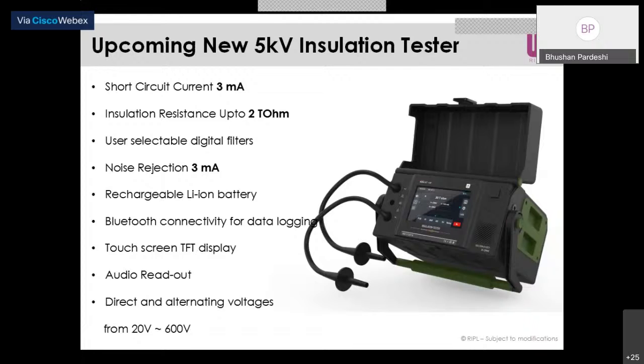The concept of the digital filter is that you can use this 2 tera ohm model up to distribution substations. But in a substation, an induction environment is created. Sometimes the competition model does not work in the induction area. This digital filter nullifies the induction voltage, and it will measure the accurate insulation resistance of the object, like transformers or circuit breakers. We have given noise rejection up to 3 milliampere. In a distribution substation, the noise will not be more than 3 milliampere, so it will nullify the 3 milliampere induction and measure the actual IR value of that object.